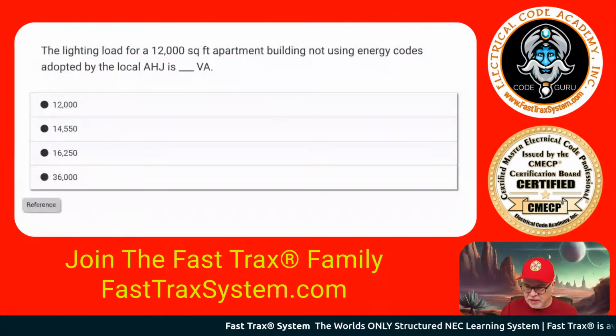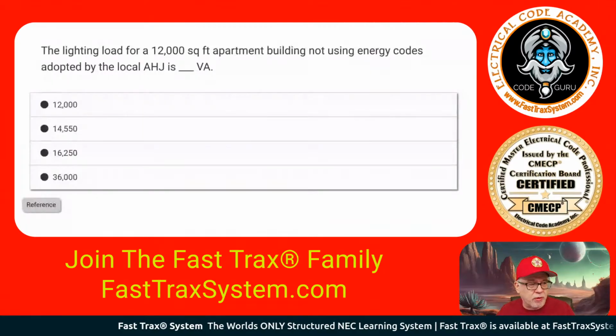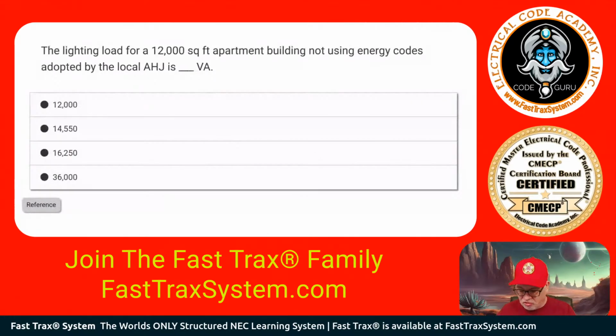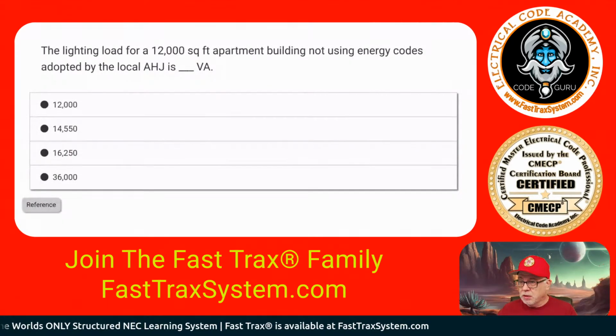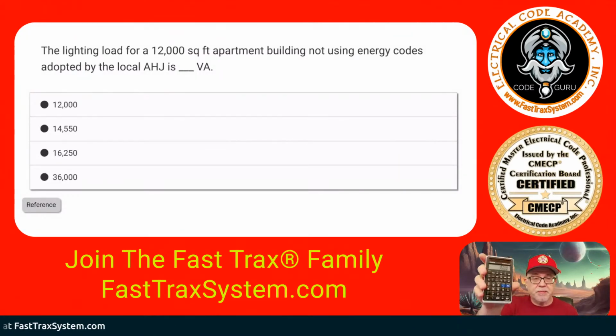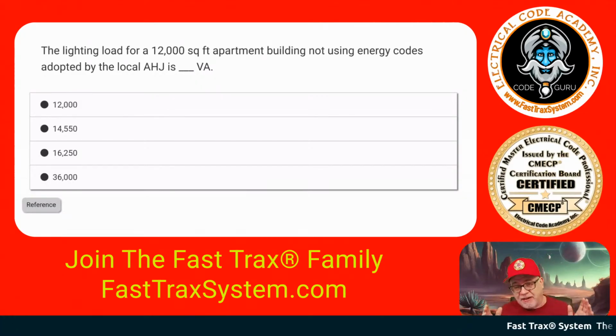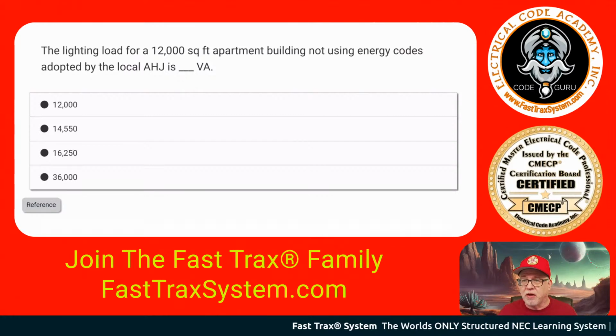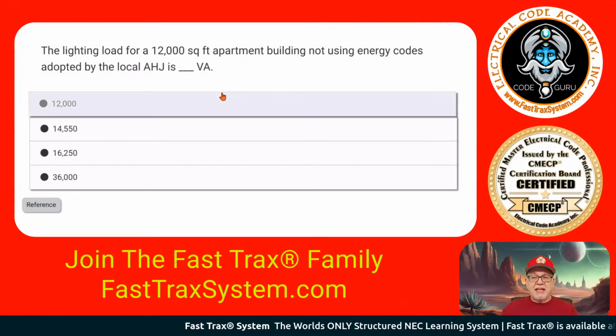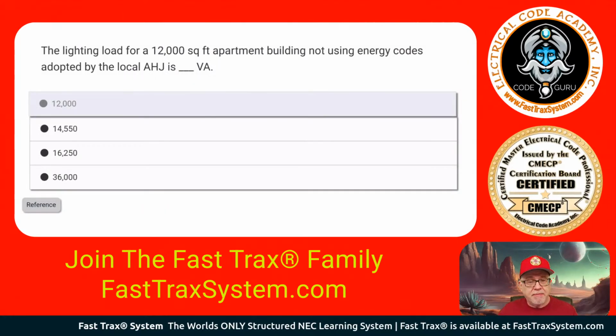And let's do a little math here. So we know it's 3 VA per square foot, right? So we're going to go, and it was 12,000. So we're going to go 12,000 times 3. That's 36,000. That is, again, it didn't ask us after adjustment and corrections. It didn't ask any of that stuff. It basically wanted to know what was the lighting load in VA.